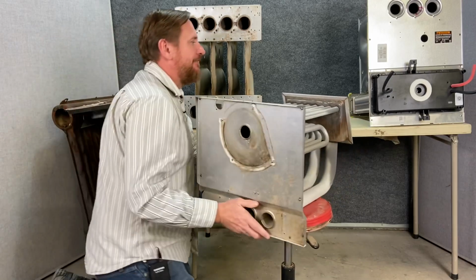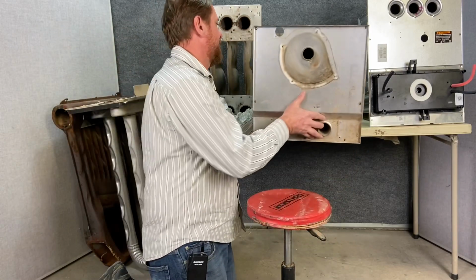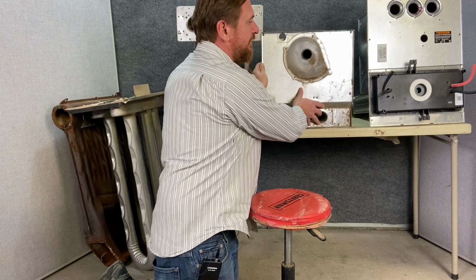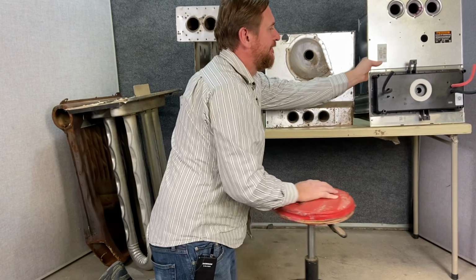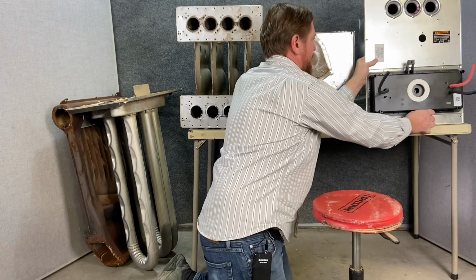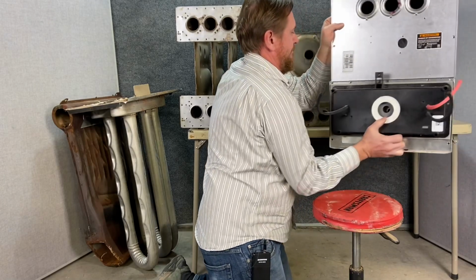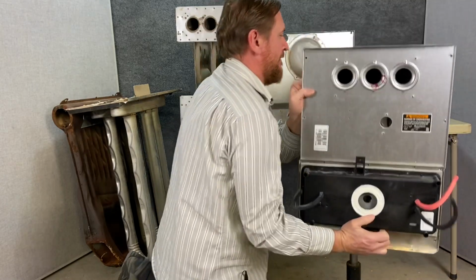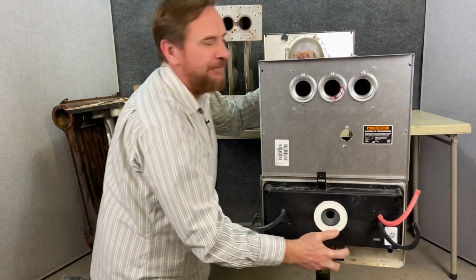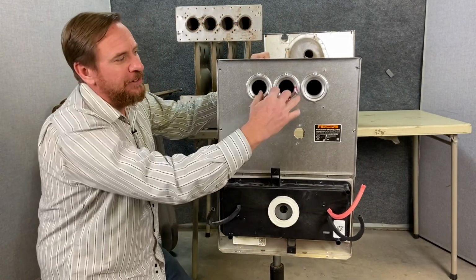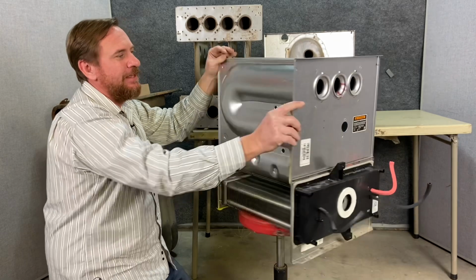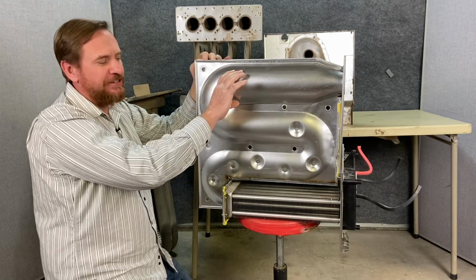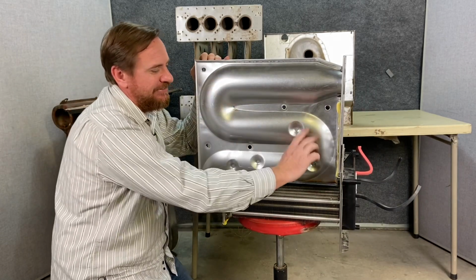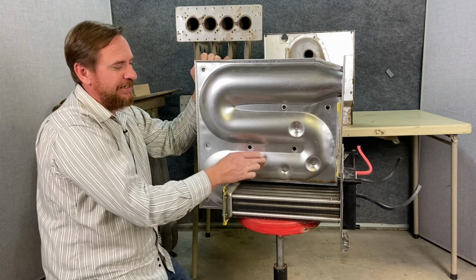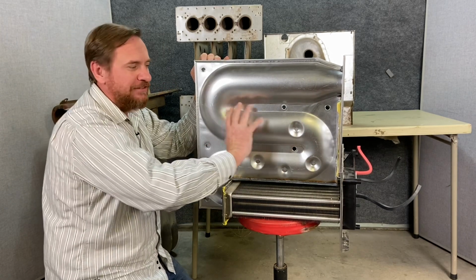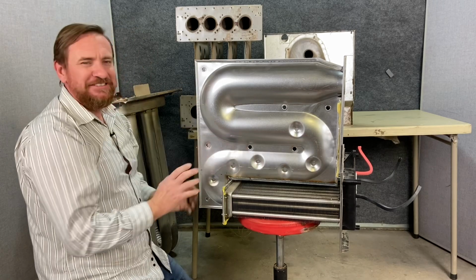Now we have my favorite type of gas furnace, which is a 90 plus condensing furnace. So in this furnace, our flames are actually burning into the very top side. This is my combustion chamber section. Then we pull the gases down. We have all these little rivets or divots in here. These allowed us to make more surface area. But this is the beautiful part.